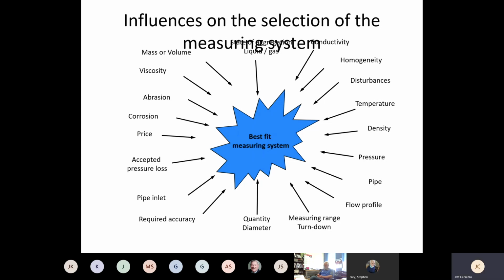Some of these we talked about, but other considerations: the viscosity of the liquid. Is it corrosive? Is it abrasive? Again, what's your pressure loss? What kind of piping? What's your required accuracy? What do you need for turn down? What's the flow profile going to look like? What's the temperature? Many of the meters are limited in temperature to 200-300 degrees on up to 800 degrees. So we need to know those types of things. What's the homogeneity of the liquid? Is it got air entrained? Is it conductive? And of course, a lot of times it boils down to price. We all want the world, and then when the sales engineer tells you what the price is, we sometimes back off a little bit and say, okay, what else can we do? So we can help with all those types of things.